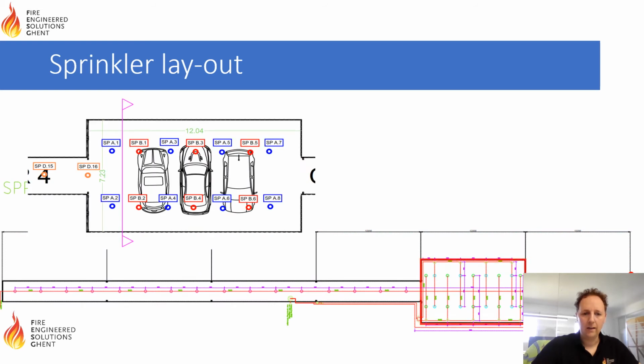Looking at the sprinkler layout, the middle car was the one where we would always ignite the fire on the passenger seat. The window of the driver's seat would remain open. And we had 2 setups, either the red sprinkler system with sprinkler heads on these positions, or the blue sprinkler system with the sprinklers in between the cars would be activated.